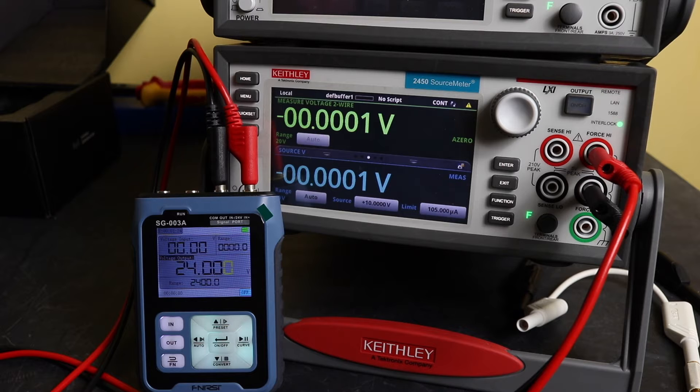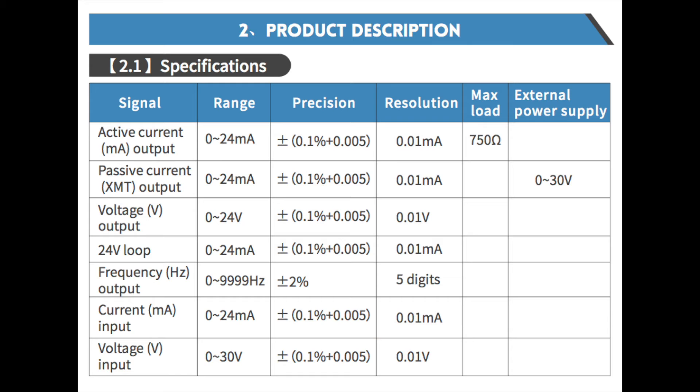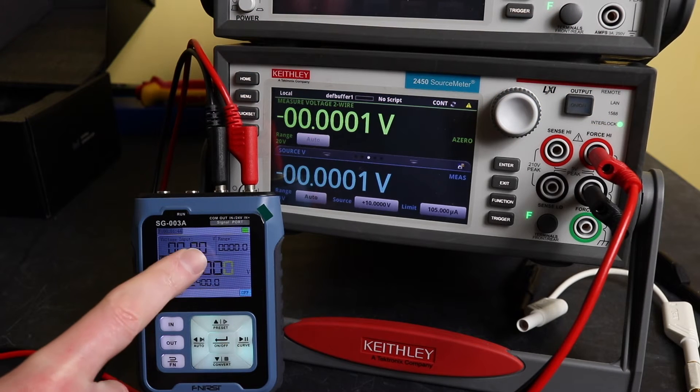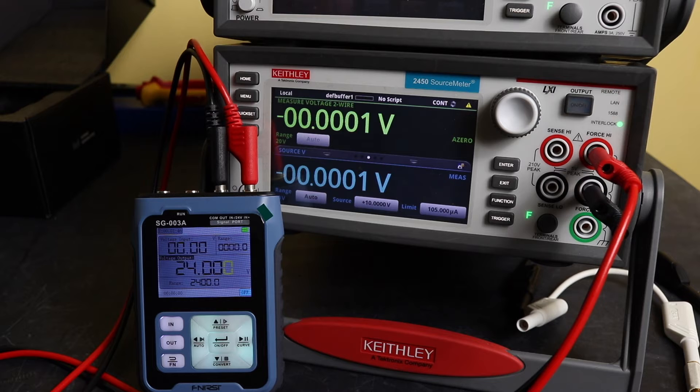I didn't compare it to their actual specifications, which I'll put this table up now. You can see that their specifications are predominantly 0.1% plus 0.005 digits. I do have a bit of an issue with that because on the voltage input you can't get down to what would be 5 millivolts. 10 millivolts is the resolution of the display.